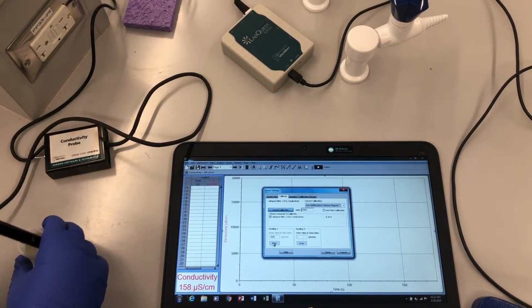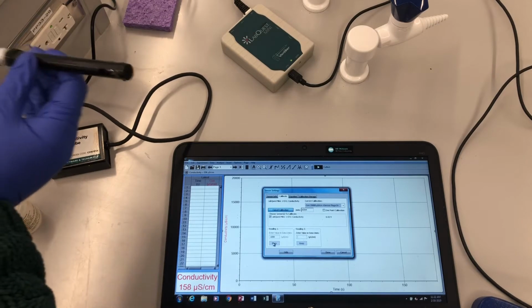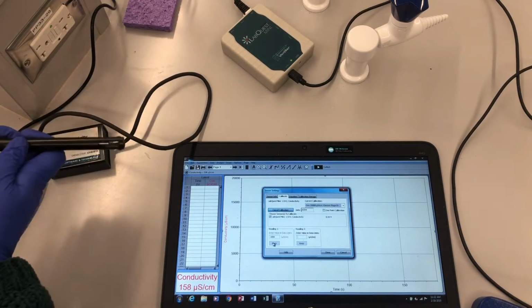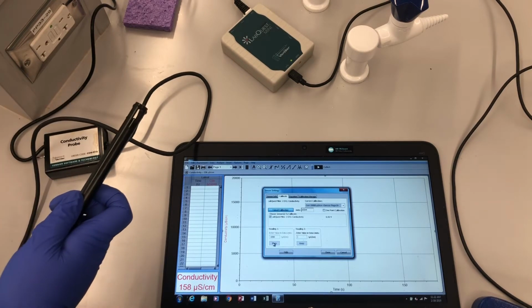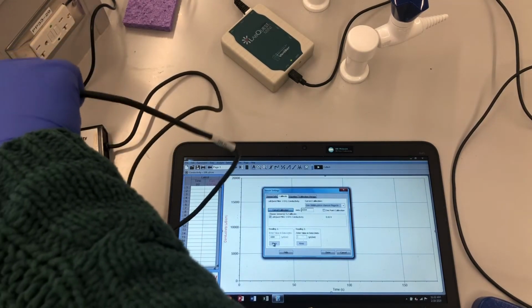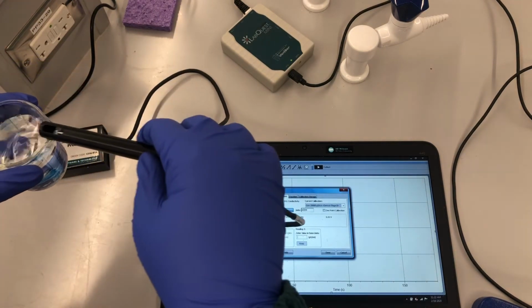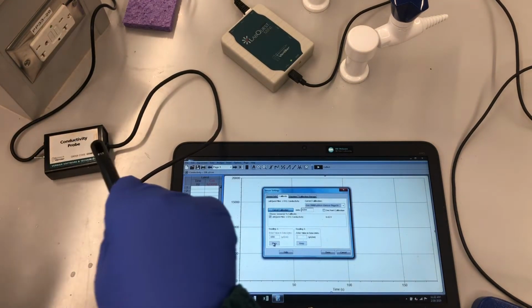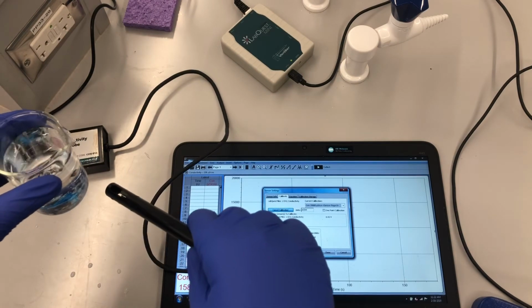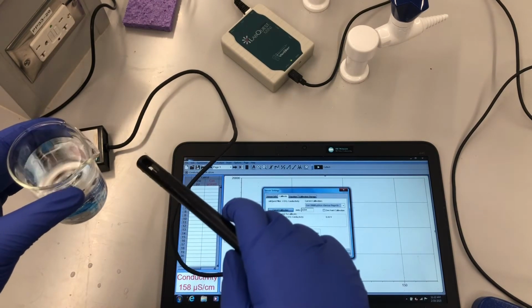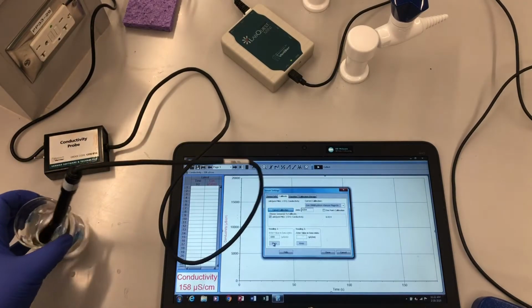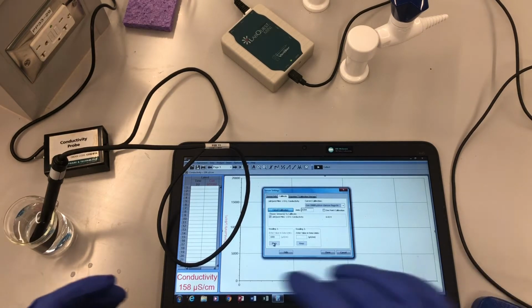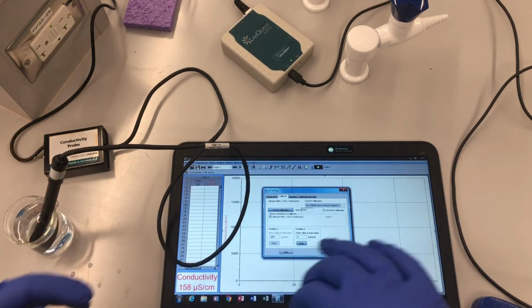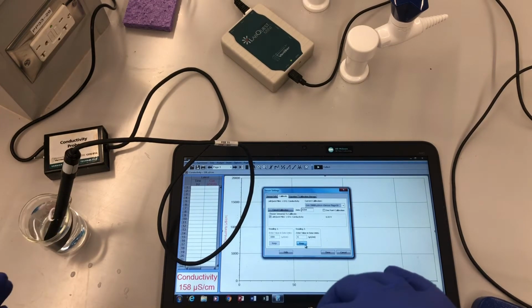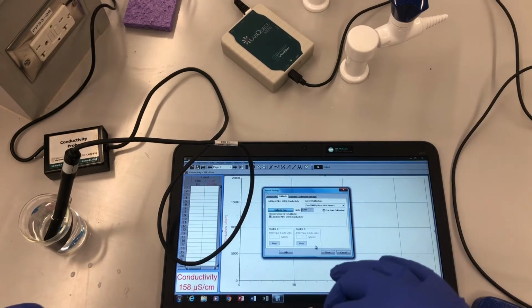All right, now that that's done, I'm going to take this out, close this back up. Don't want it to spill. Wash your probe in some DI water to make sure it's all clean. Always wash your probe in between uses. Let it dry a little bit. And then take some DI water, and we're going to use this as our second standard. This is going to be at 0 microsiemens because DI water is filtered and there's nothing floating around in it that can conduct electricity. There's no ions. So I'm going to use my second value as 0. You can see that the probe's still in there. I'm going to hit keep. And done. That's it.